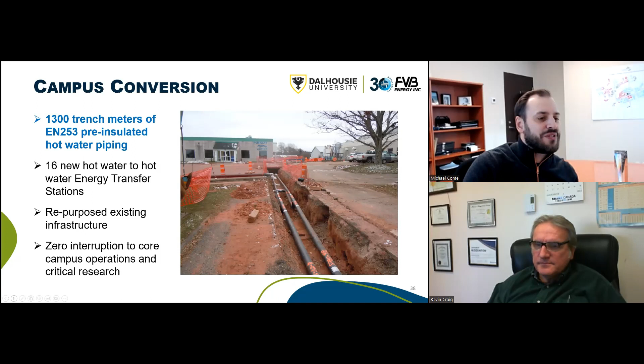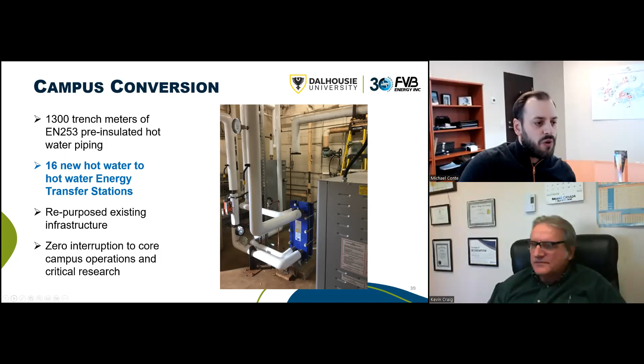In addition to this, we had to install 16 new hot water energy transfer stations. The campus was set up so most buildings took hot steam and converted it to hot water at the entrance to the building. For a number of buildings it was just a matter of swapping heat exchangers, but there were buildings that took steam right to the terminal units, including everything from humidifiers to sterilizers. The kitchen even took steam right to a big wok used in preparing meals. So we had to replace and convert all those systems over to accept hot water.